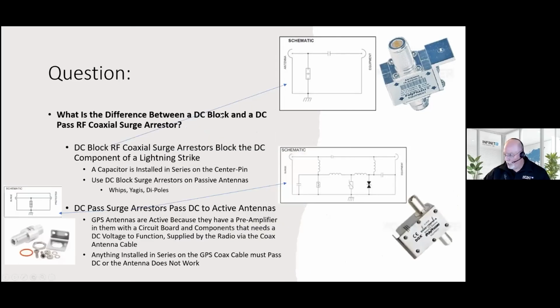What's the difference between a DC block and a DC pass surge arrestor? That's all about the antenna. If the antenna is passive, like a whip, a Yagi, or a dipole, then you would want a DC blocking surge arrestor, where we have a DC blocking capacitor on the center pin, which blocks the DC component of a lightning strike. It's just added protection.